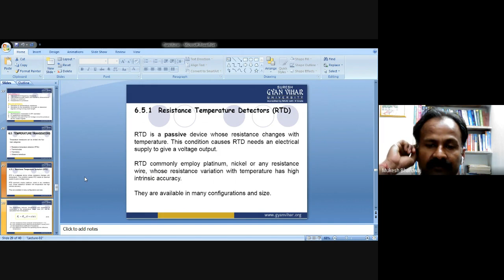RTDs commonly employ platinum, nickel, or any resistance wire whose resistance variation with temperature has high intrinsic accuracy. They are available in many configurations and sizes. The relationship between temperature and resistance of the conductors in the temperature range near 0 degrees centigrade can be calculated from the equation R_T equals R reference times (1 plus alpha delta T). So R_T is the resistance of the conductor at temperature T in degrees Celsius. R reference is the resistance at the reference temperature, usually at 20 degrees centigrade. Alpha is the temperature coefficient of resistance, which can be negative or positive, and delta T is the difference between the operating and the reference temperature.